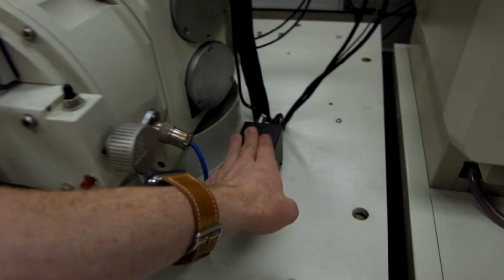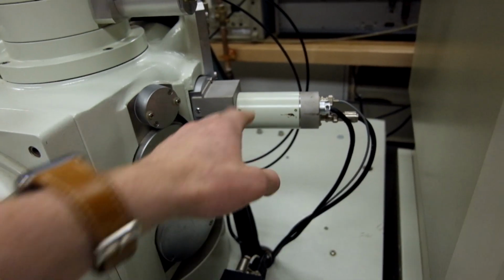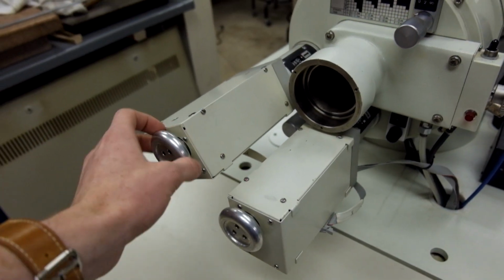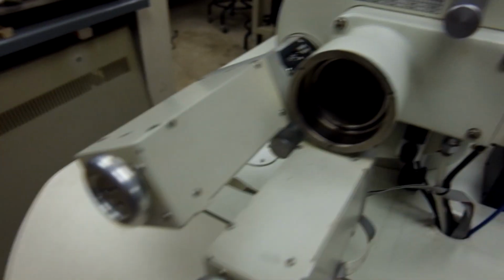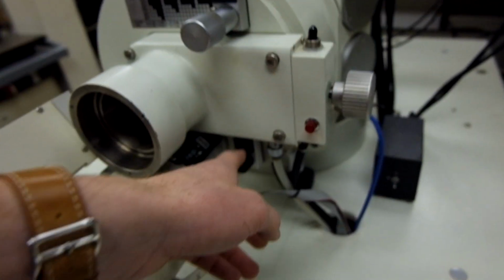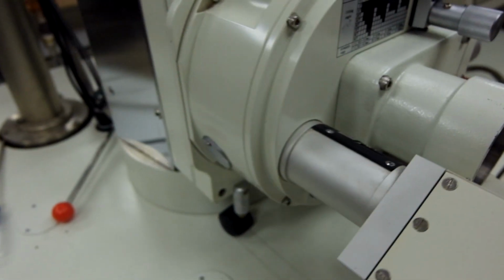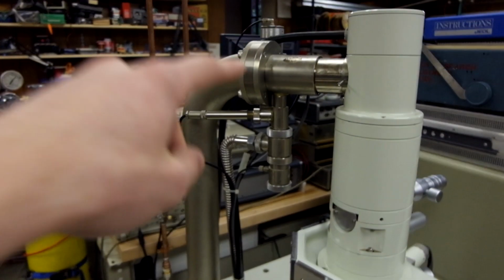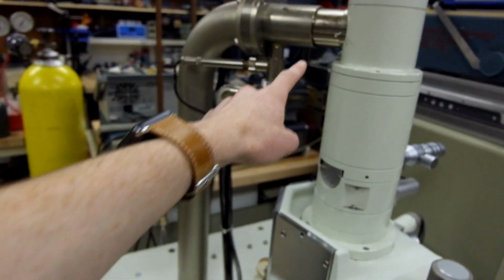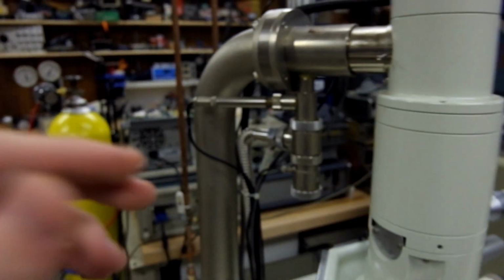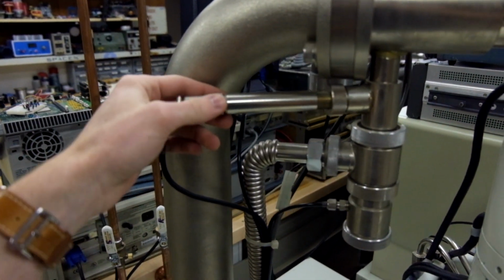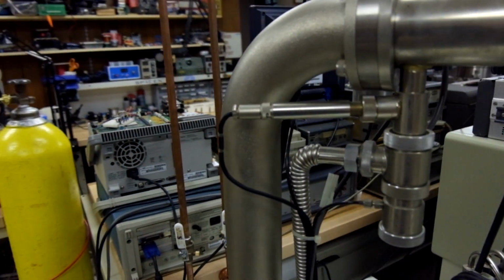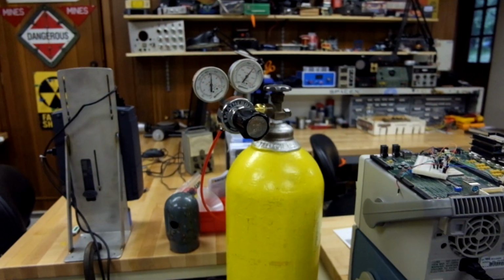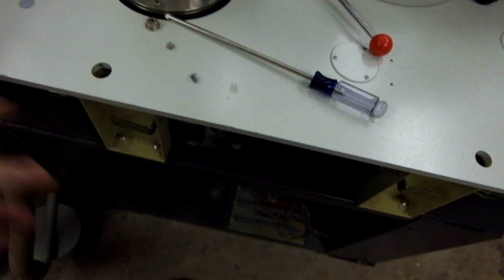This down here is the backscattered electron preamplifier. This is the secondary electron detector, and these are motorized XY manipulators that go down to a micron. These are very nice. There's stage tilt and rotation and all kinds of other adjustments around there. This is the evacuation manifold, so this is what evacuates this area down to high vacuum. This is one of those Pirani gauges I was talking about, so I tapped into one of those on that multimeter. It requires a nitrogen cylinder, that's right here, and there's all kinds of solenoids and stuff in here.